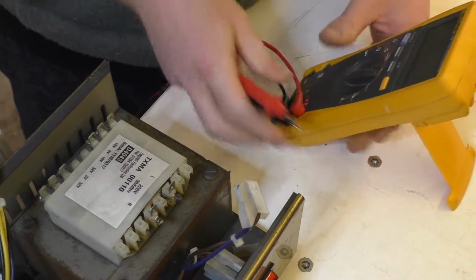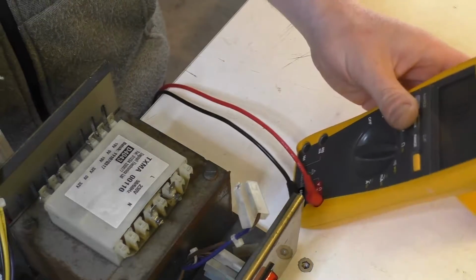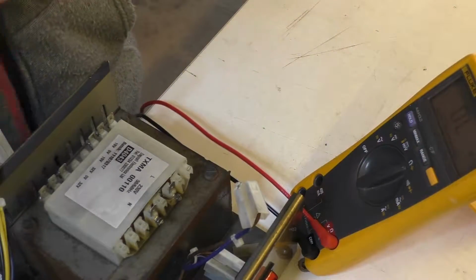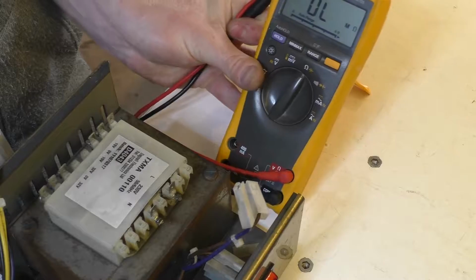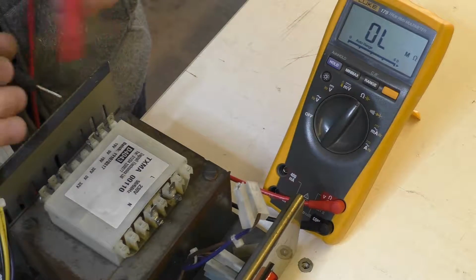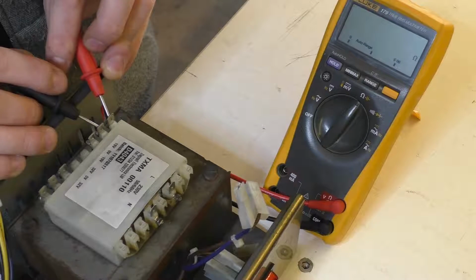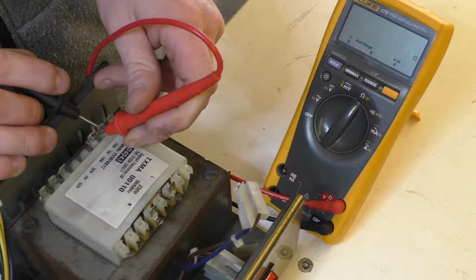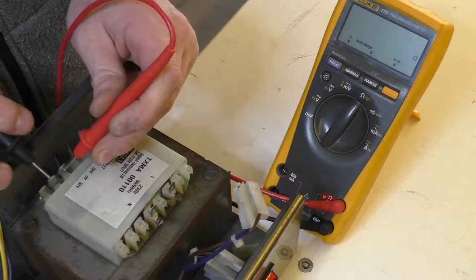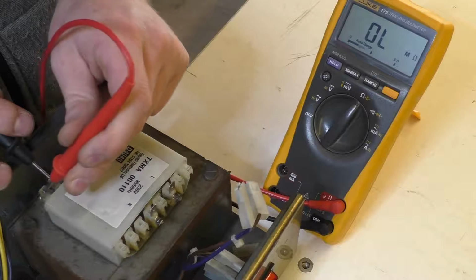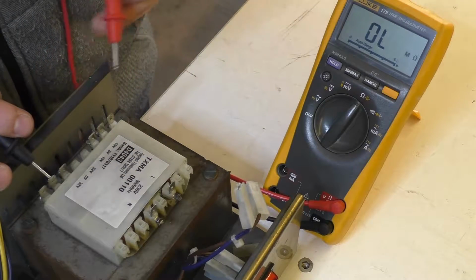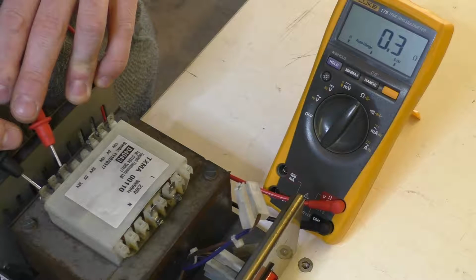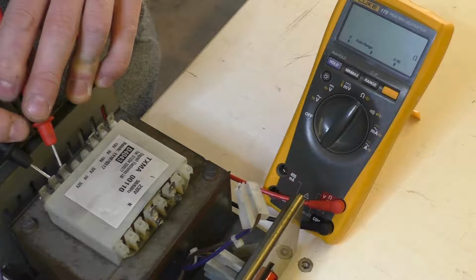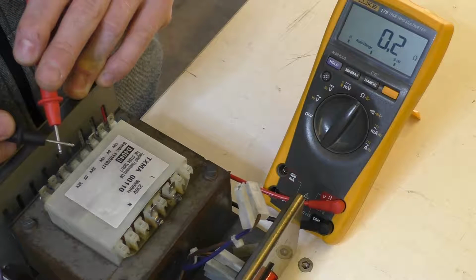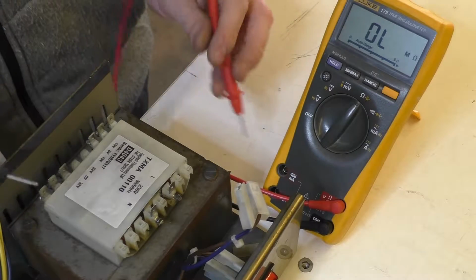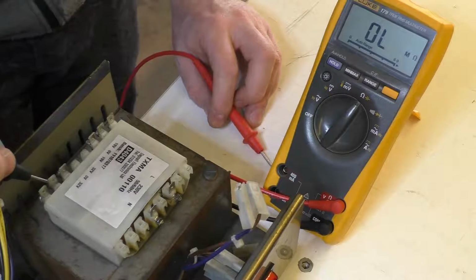Just check the resistance between, see that there? There we go. Between the two halves of the windings. 1.2. 1.2, that's right. 0.3. 0.3, so that'd be a beefier winding because it's got more current. 0.3. The leads are probably 0.1. 0.2, 0.1, so there's a bit of an error happening there.